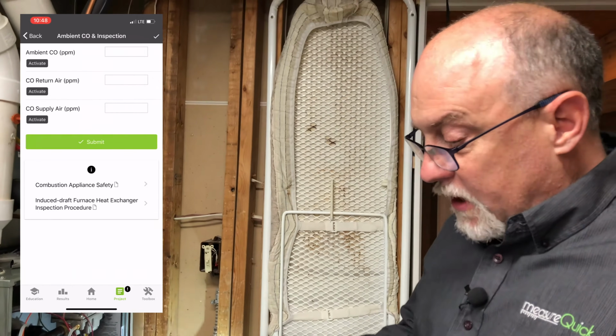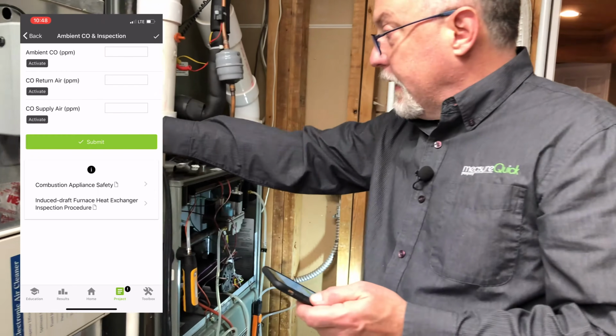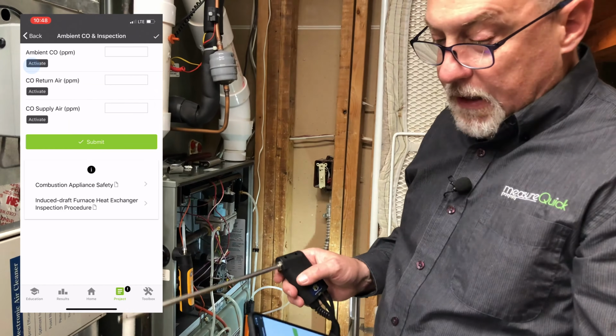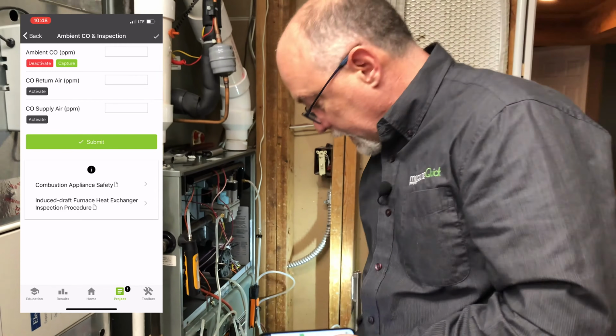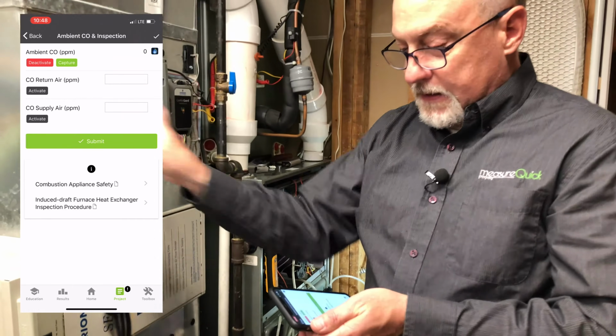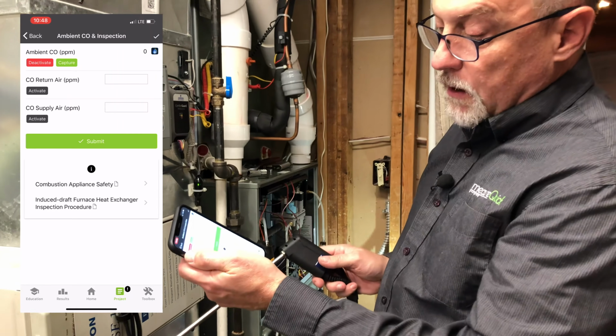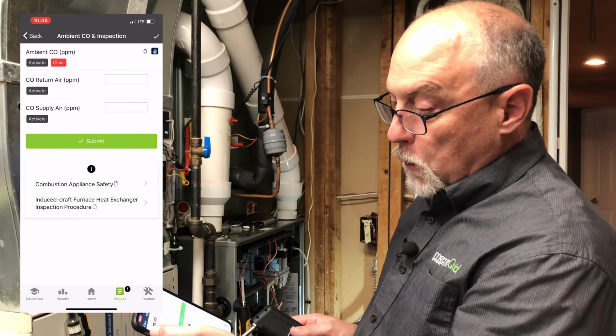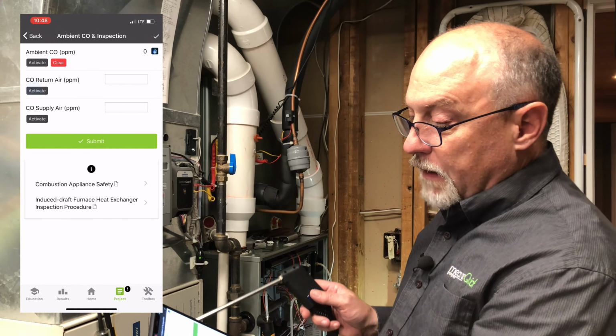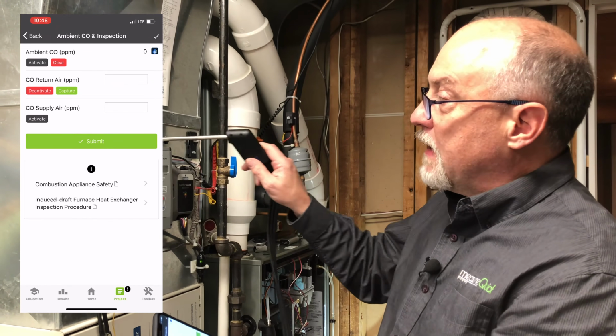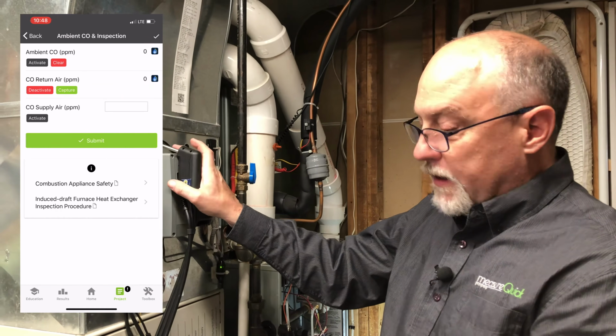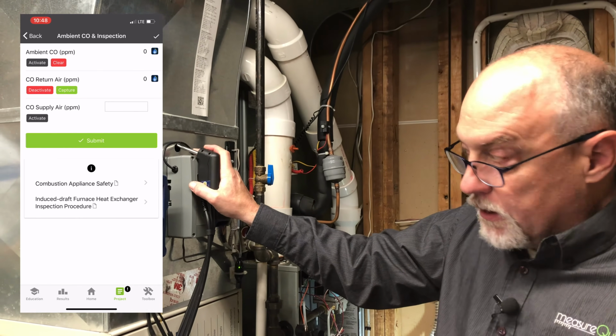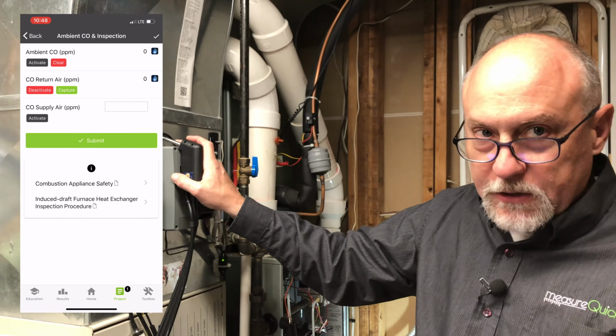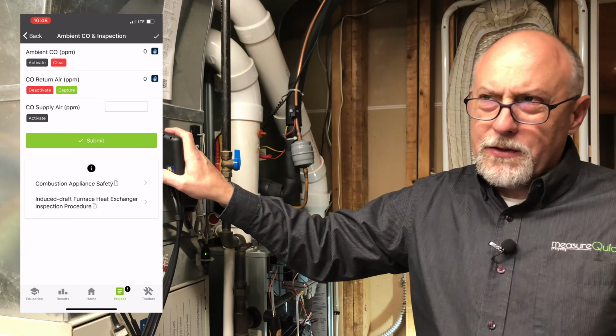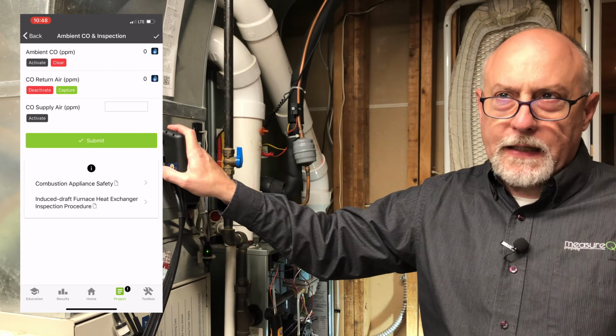I'm going to hit ambient CO inspection, and again I'm going to activate my combustion analyzer. What you'll notice is that it's going to show 0 ppm ambient on here, and I'm going to hit capture. So now I'm going to activate my return, and you need to give this a couple seconds in the return air, probably about a good minute or so. What you're waiting for is to see if there's any carbon monoxide. And you're going, well, there's no CO in the air. Where else would I get it from?